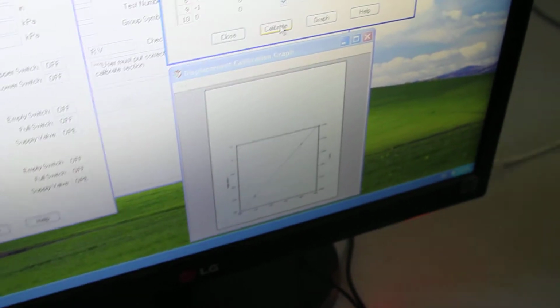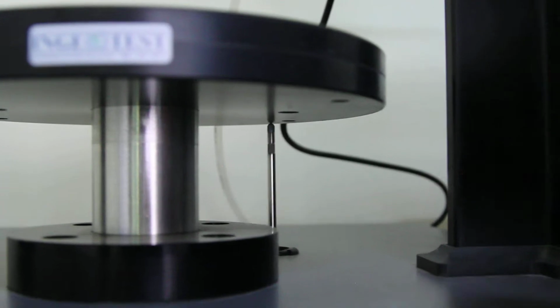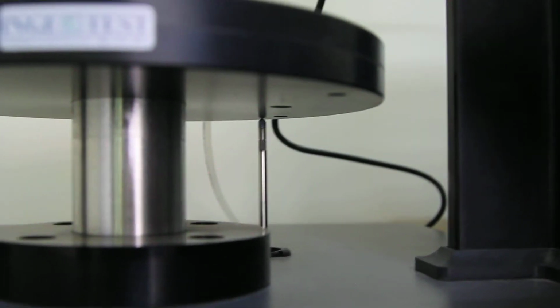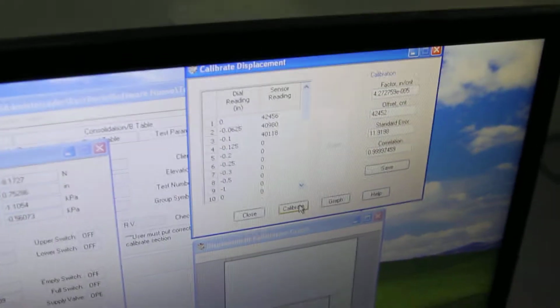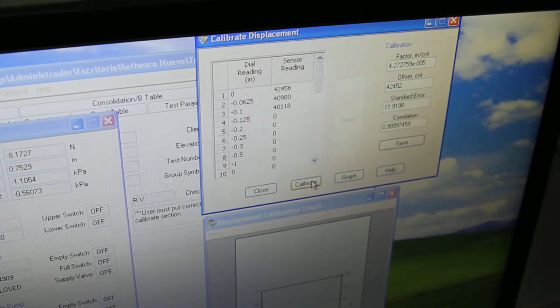The next step is I am going to remove my first gauge block and insert the next one. Next one is 0.1, and so now I have the next point. So I go back to my software and do read again. Now I have 3 points. Do calibrate, so I can see my calibration taking place.